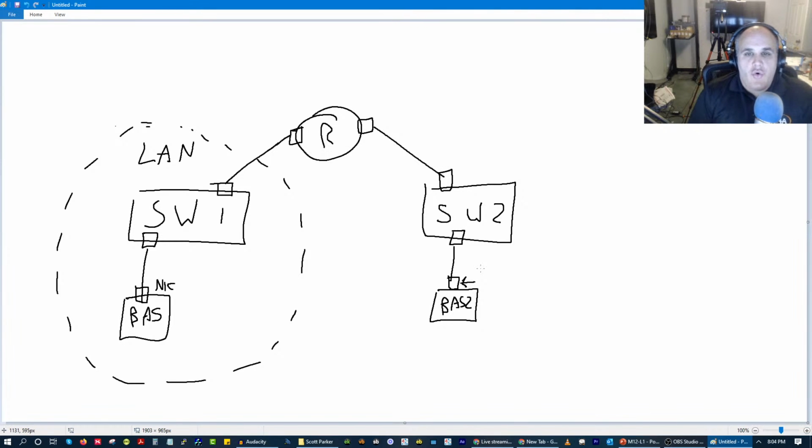All right, so how all of this works is you have these physical addresses and logical addresses. So the physical address, in the case of our BAS devices, is going to be known as the Ethernet MAC address. So very similar to MAC address on MSTP devices, except in this case, it's using hexadecimal, and it is for Ethernet protocol, not for MSTP. So the MAC address acts as the physical address for the device. It is unique to that device.